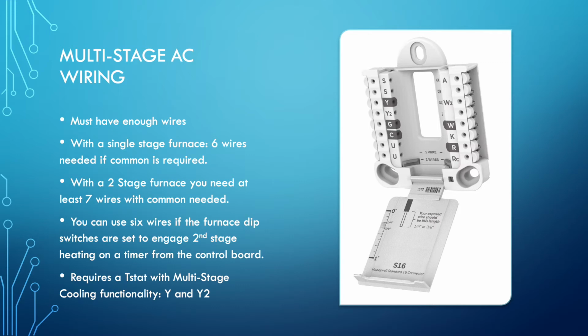be on Y2. What's not acceptable is to wire Y and Y2 together out at the air conditioner so that when the system calls for cooling, it brings on both stages simultaneously. Now that is a technician temporary field fix when something's gone wrong and we need to do that. However, if it is a customer that has paid to have a two-stage cooling system put in, we need to give them that capability. They need to get their money's worth and the value that we're offering them. So make sure you have enough wires to perform that functionality.